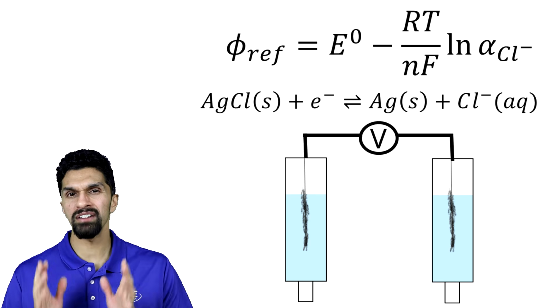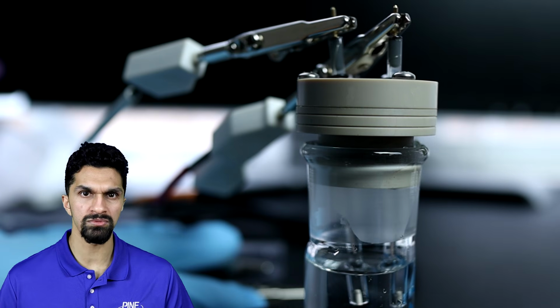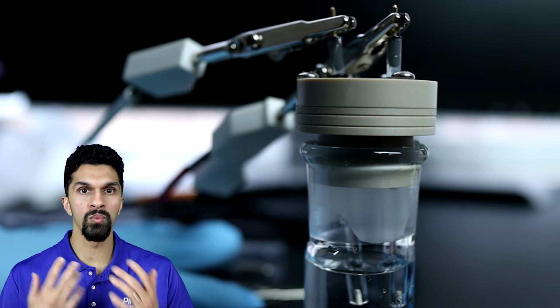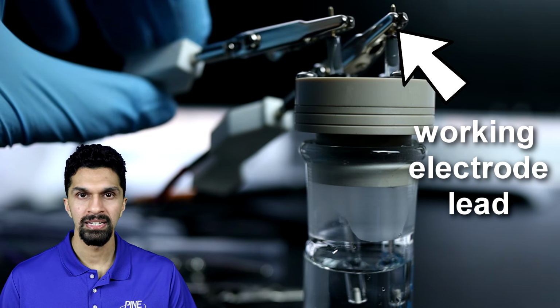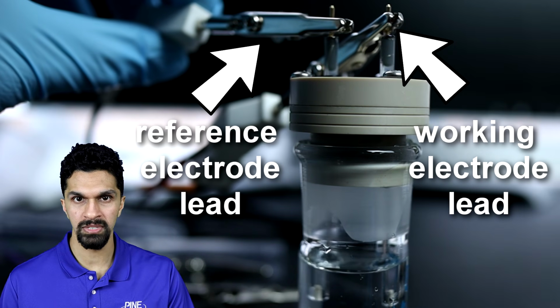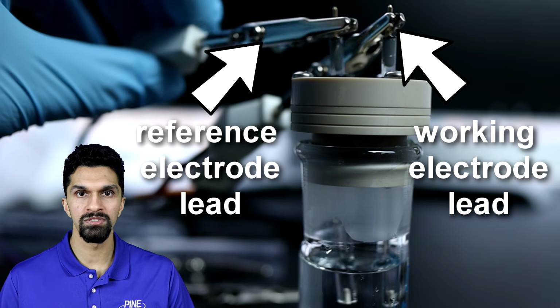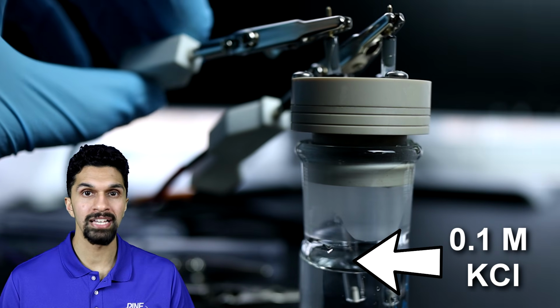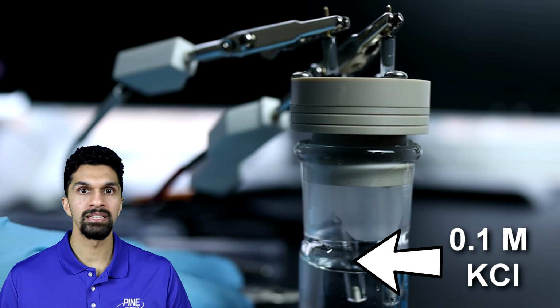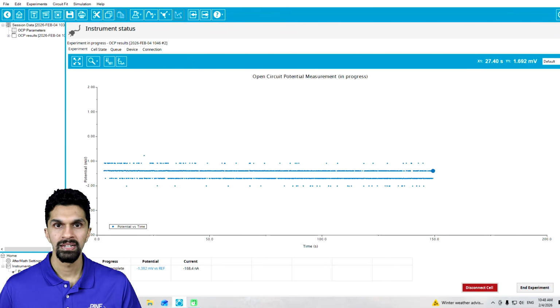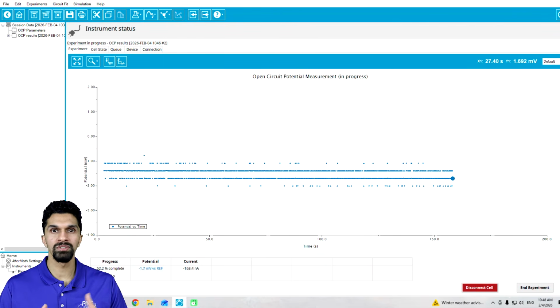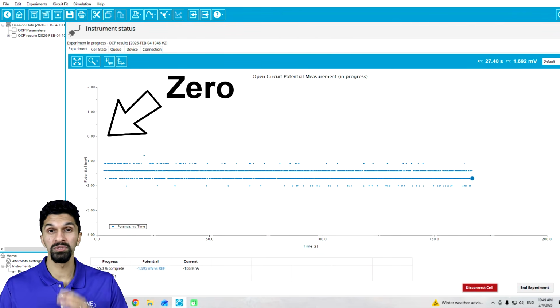For example, if I have two silver-silver chloride reference electrodes, I can connect one to my working electrode lead and the other to my reference electrode lead, submerge them into a 0.1 molar potassium chloride solution, and then measure the open circuit potential. Ideally, I should get a value of 0 or a value close to 0.